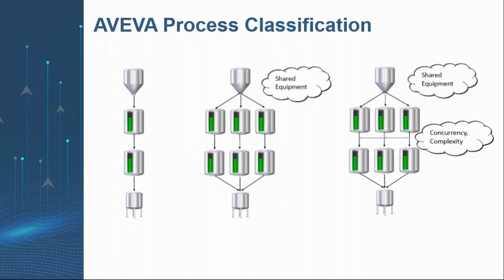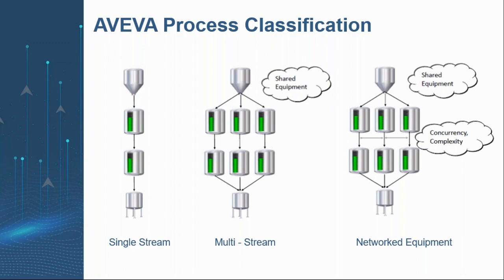No matter how complex your process is, it can be configured easily using AVEVA Batch Management — either a single, multiple, or networked stream. A single stream structure is a group of units through which a batch passes sequentially. Multiple material inputs are commonly used, and multiple finished materials may be produced. The multiple stream structure consists of multiple single stream processes in parallel with no product transfer between them; however, they typically share the same raw material sources and product storage. Networked streams are the same as multiple streams, but there is product transfer between them.